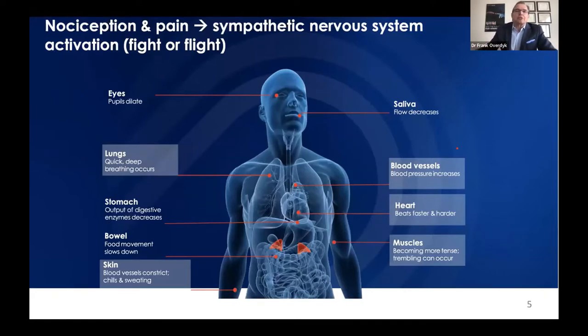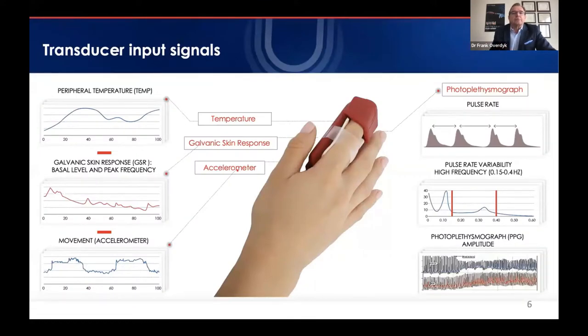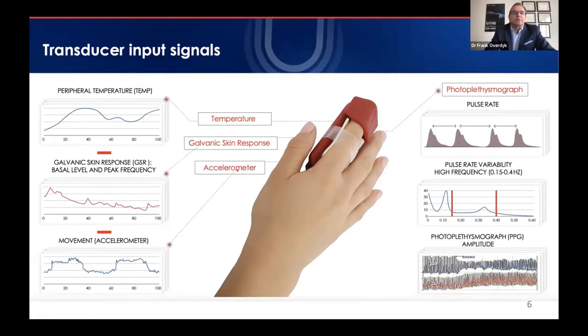Pain and nociception activate the sympathetic nervous system: pupils dilate, breathing and heart rate increase, blood vessels constrict, and sweating occurs. The NOL captures signals from several of these sympathetically activated organ systems — the peripheral vasculature, the heart, and the skin. The transducer looks like a bulky pulse oximeter. It measures the photoplethysmograph (PPG) — amplitude, pulse rate, and variability — galvanic skin response (skin conductance), temperature, and movement through an accelerometer. Temperature and movement do not contribute to the NOL score but help assess signal quality.